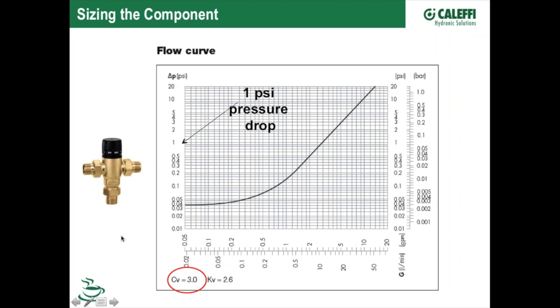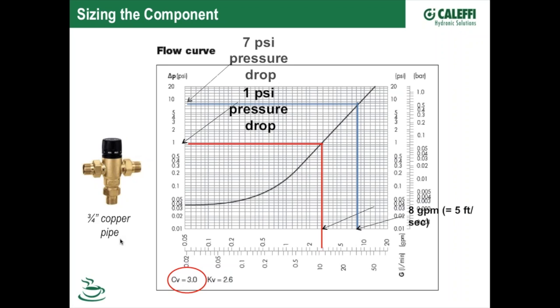So you say, well, I want to use this on a domestic water application, and they've got a body spray in their shower, and they need, I don't know, let's say 8 gallons a minute or 7 gallons a minute. They need a higher flow rate than what the valve says on the label of the box. What's going to happen? So here we are, 3 gallons a minute, 1 pound pressure drop. Now let's say we're piping this with 3/4 copper pipe, and now we want to look at an example with a higher flow rate. Again, let's apply that body spray.